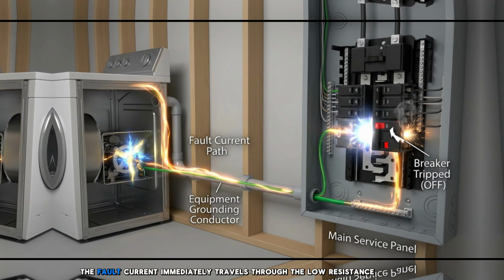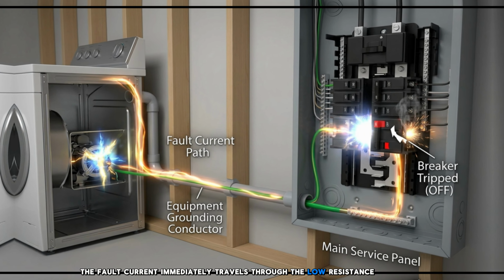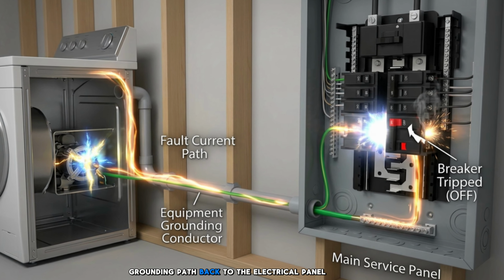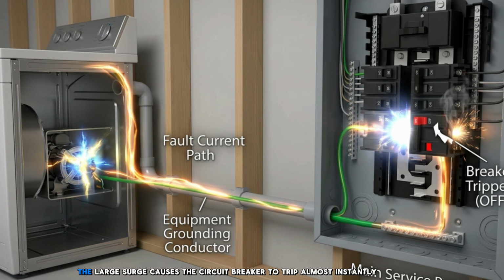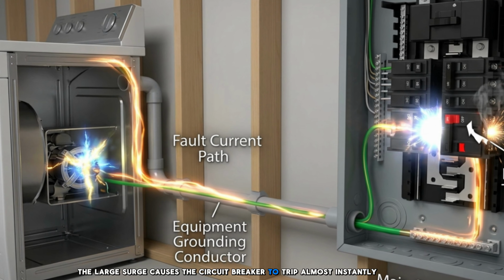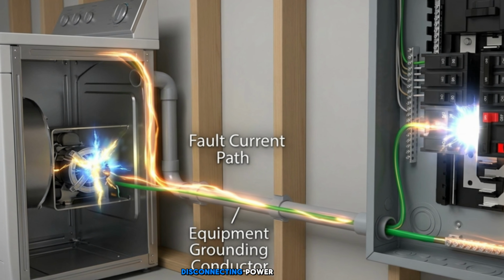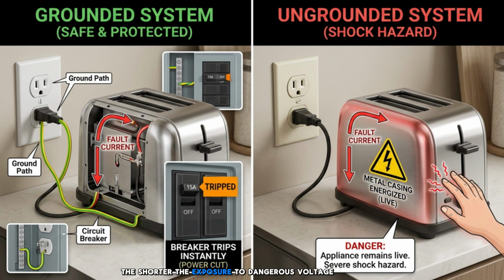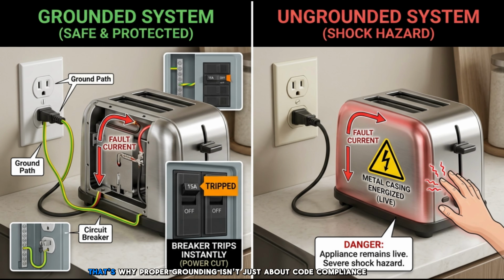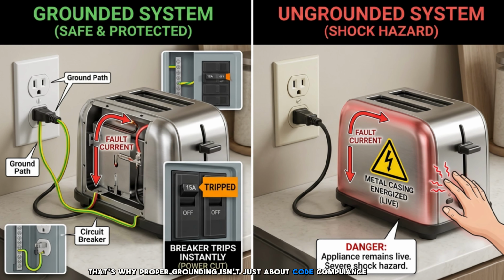With a properly connected equipment grounding conductor, the fault current immediately travels through the low-resistance grounding path back to the electrical panel. The large surge causes the circuit breaker to trip almost instantly, disconnecting power. The faster the breaker trips, the shorter the exposure to dangerous voltage. That's why proper grounding isn't just about code compliance, it's about protecting lives.